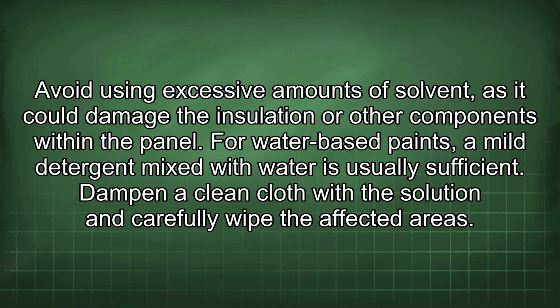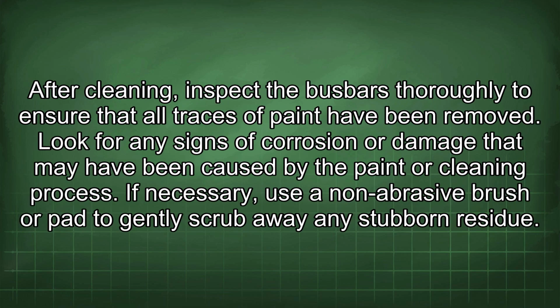For water-based paints, a mild detergent mixed with water is usually sufficient. Dampen a clean cloth with the solution and carefully wipe the affected areas. After cleaning, inspect the busbars thoroughly to ensure that all traces of paint have been removed. Look for any signs of corrosion or damage that may have been caused by the paint or cleaning process. If necessary, use a non-abrasive brush or pad to gently scrub away any stubborn residue.